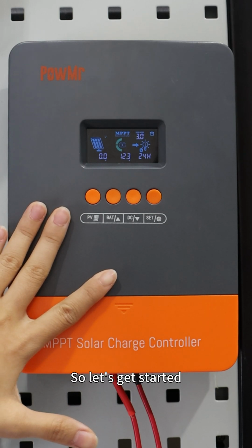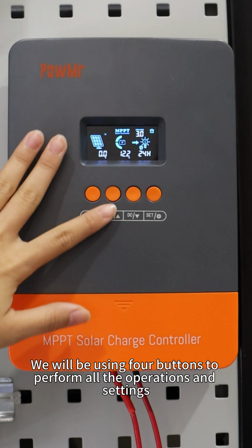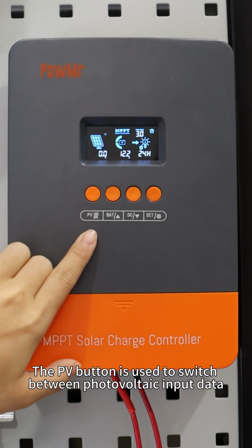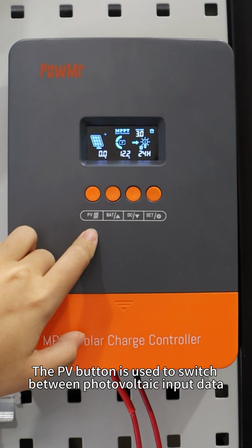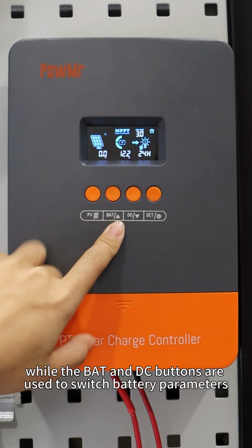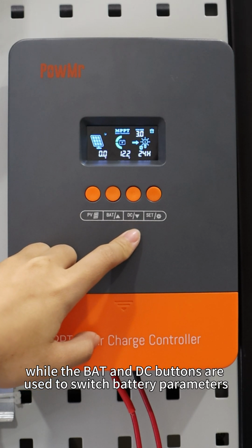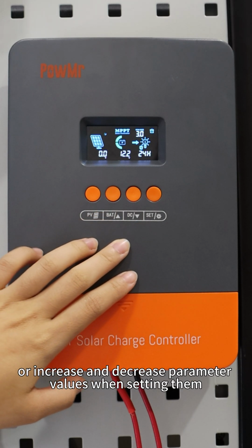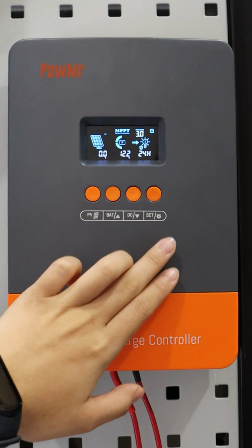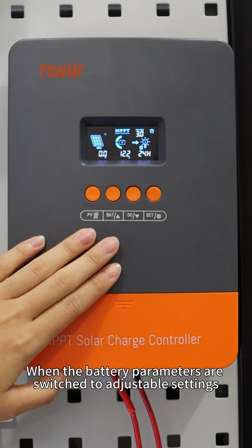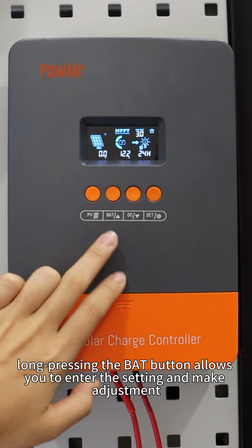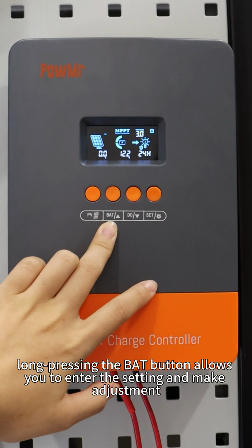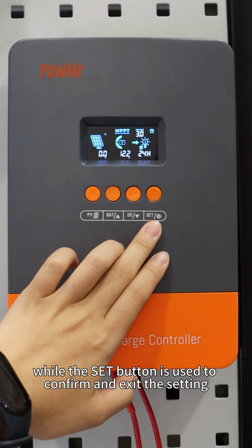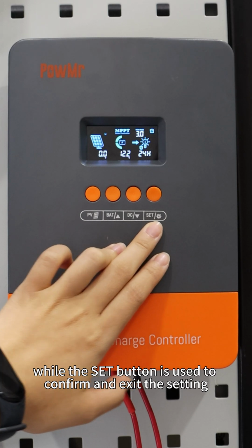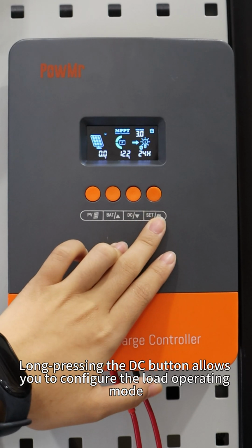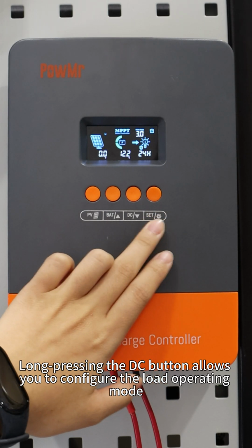So let's get started. We will be using four buttons to perform all the operation and settings. The PV button is used to switch between the photovoltaic input data, while the BAT and DC buttons are used to switch battery parameters or increase and decrease parameter value when setting them. When the battery parameters are switched to adjustable settings, long pressing the BAT button allows you to enter the setting and make adjustments, while the SET button is used to confirm and exit the setting. Long pressing the DC button allows you to configure the load operating mode.